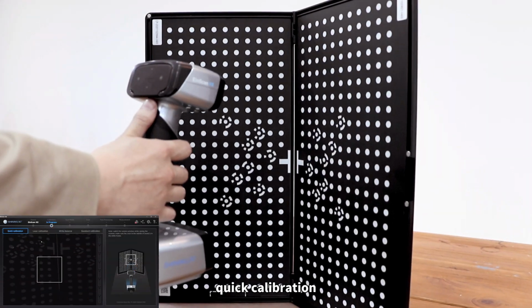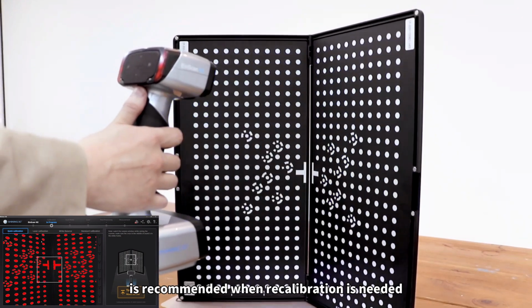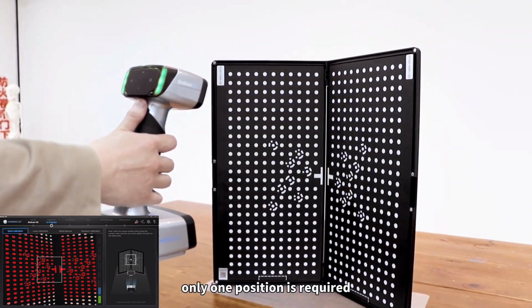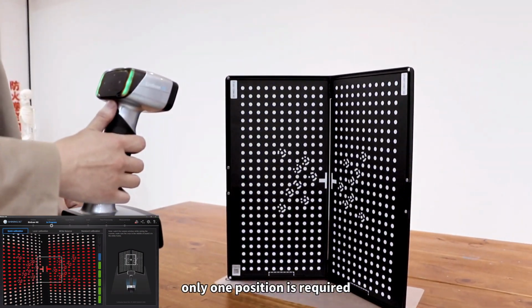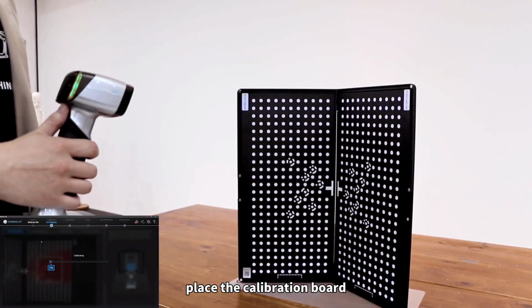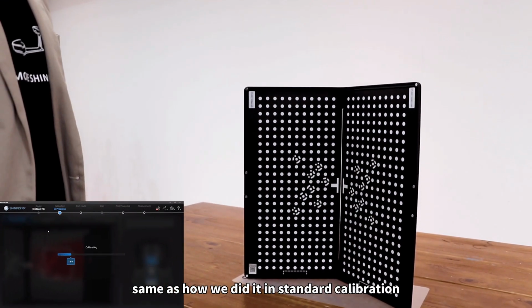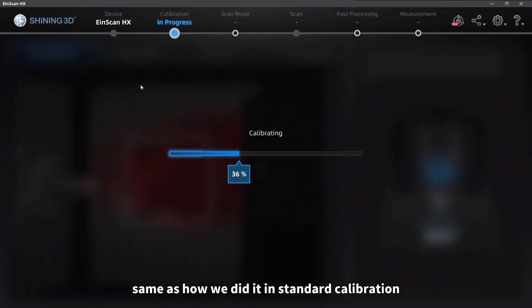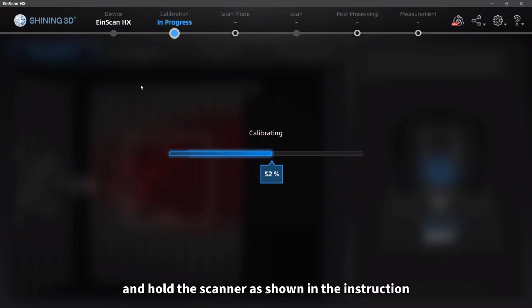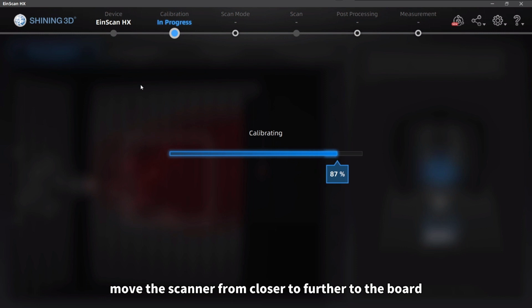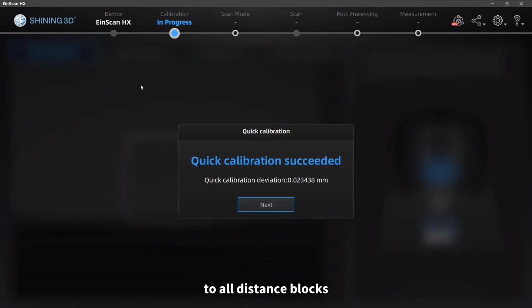Quick calibration is recommended when recalibration is needed. Only one position is required. Place the calibration board the same as how we did it in standard calibration and hold the scanner as shown in the instruction. Move the scanner from closer to further to the board till all distance blocks turn into green.